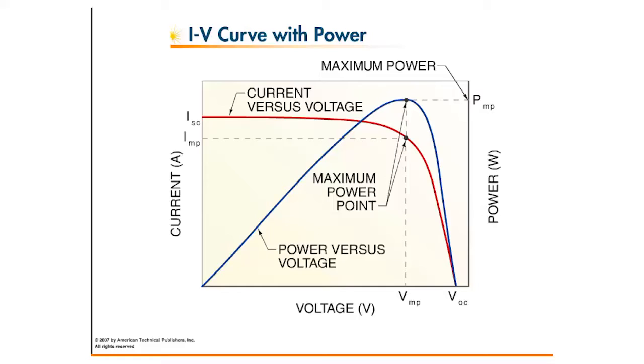And so it's a current limited source, which all of us know, but we have to remind ourselves that we have a short circuit current that is absolutely limited. It's limited by how much sunlight we've got. We have an open circuit voltage that's absolutely limited by the number of cells we put in series and things like that. Our power versus voltage curve, obviously we want to operate this thing on the knee of the curve and all that stuff. And that's how we design our systems, and we have inverters that do that for us.